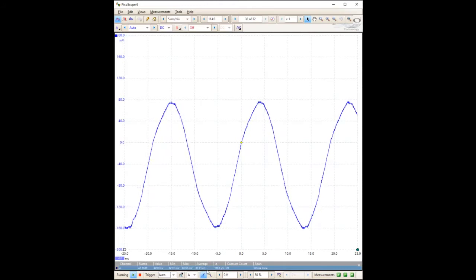And down here at the bottom you can measure parameters. So we're measuring 82.8 millivolts as an average RMS reading. It's 10 millivolts per amp, so it's currently running at 8.3 amps. And in this way I can get good accurate measurements of the current independent of the generator control system.